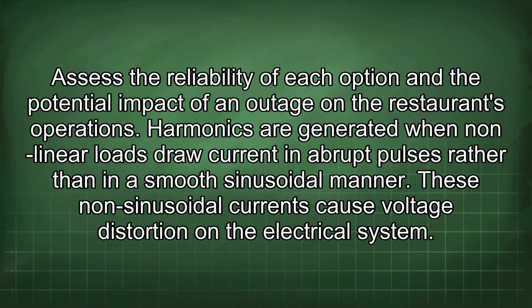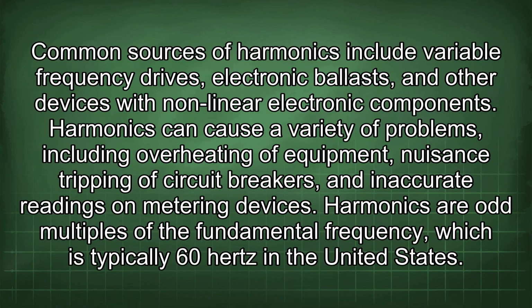Harmonics are generated when nonlinear loads draw current in abrupt pulses rather than in a smooth sinusoidal manner. These non-sinusoidal currents cause voltage distortion on the electrical system. Common sources of harmonics include variable frequency drives, electronic ballasts, and other devices with nonlinear electronic components. Harmonics can cause a variety of problems, including overheating of equipment, nuisance tripping of circuit breakers, and inaccurate readings on metering devices. Harmonics are odd multiples of the fundamental frequency, which is typically 60 Hz in the United States.